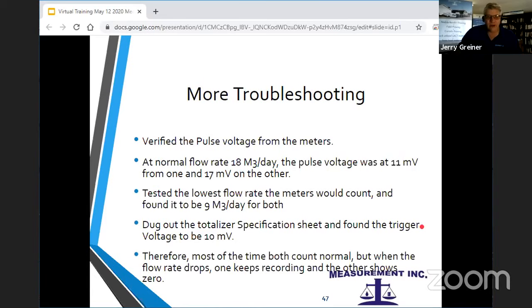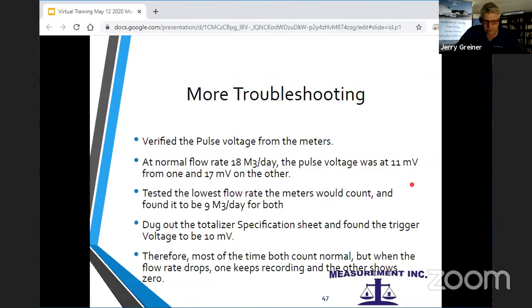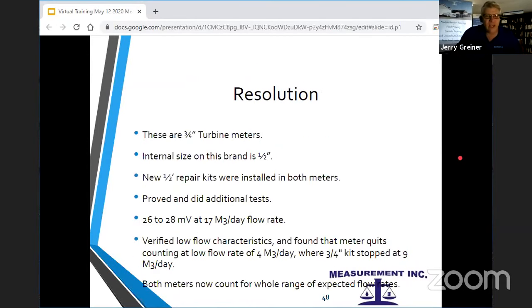And so what we found is these ones would count good, but the one that had the lower millivolt output at 18 would actually quit counting just below 18. It would drop about 17 cubes a day. It would get to the 10 millivolt and it wouldn't count. What we did for resolution is we found they're 3/4 inch turbine meters, and on this particular brand, a 3/4 inch is really a 1/2 inch. Most turbine meters are like that. 3/4 and 1/2 are the same body with a different kit. So we were just able to put in 1/2 inch repair kits in these.